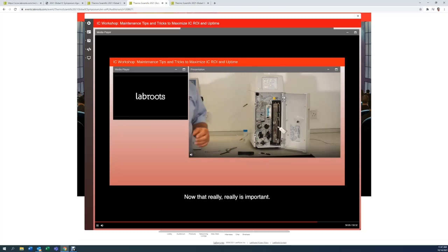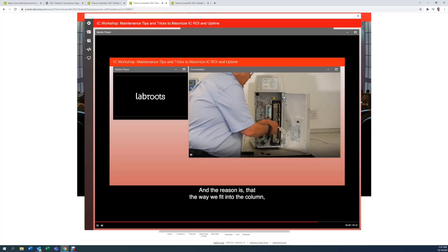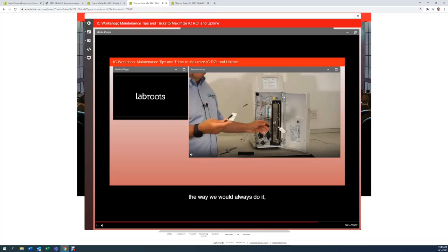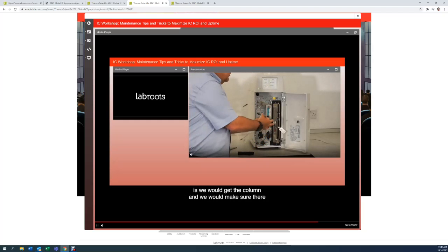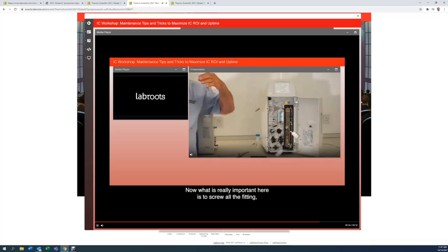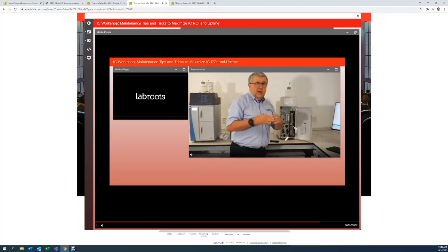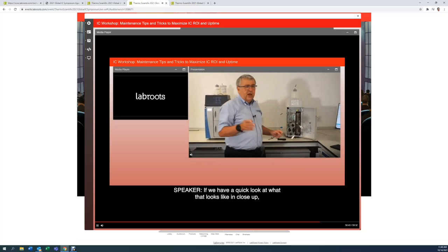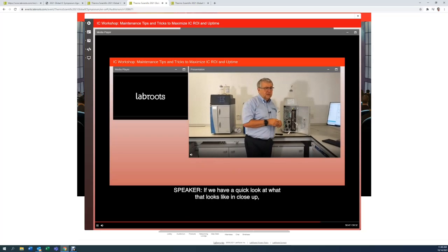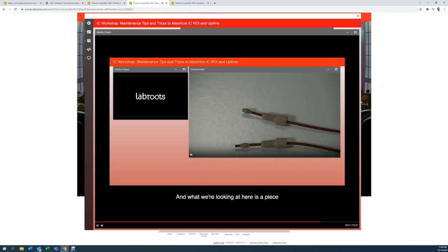Now that really is important. The way we fit into the column, the way we would always do it, is we would get the column and make sure there is plenty of tubing coming out outside the ferrule, and then we would introduce the fitting and the tubing, push the fitting down and screw it down. What is really important here is the screw or the fitting which is pushing the ferrule down to hold the piece of tubing in place. If we have a quick look at what that looks like in close-up, we can see what it should look like. What we're looking at here is a piece of tubing coming out, and that's perfect. Now, it is the tubing that's making the seal. It's not the ferrule that's making the seal. The ferrule is only holding the tube in place.